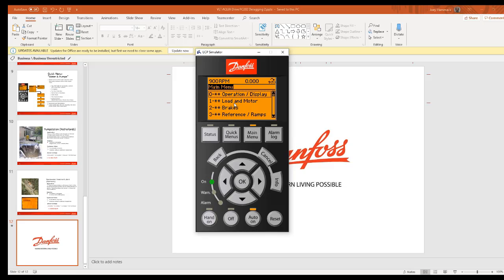And you can use them both at the same time. You don't have to just use one or the other. You can have both, every start and every stop, and when it detects power while running. So you can use both. It's just whichever you need based on the application, what kind of problems you're seeing. And if it's a brand new installation and you're not having a problem, it kind of depends on the area. If there's a lot of sediment or junk that can get in, then turn it on.